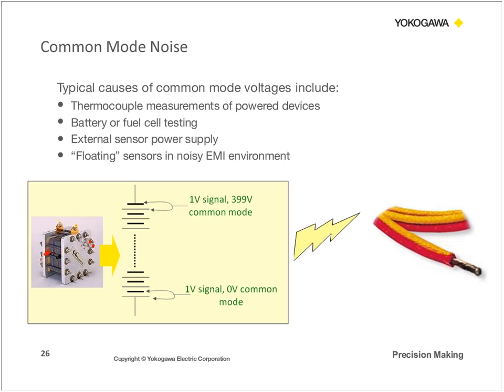So what are the common causes of common mode voltage? No pun intended. Common mode voltage can typically occur if you're making thermocouple measurements across powered devices. So this could be, for example, an industrial automation plant or a motor and drive application, or even battery cell testing where you're making thermocouple measurements across multiple points. And what you're going to have is some common mode voltage that occurs in between the channels. Another situation is also fuel cell testing as well as battery testing.